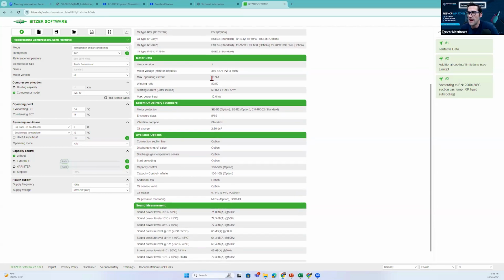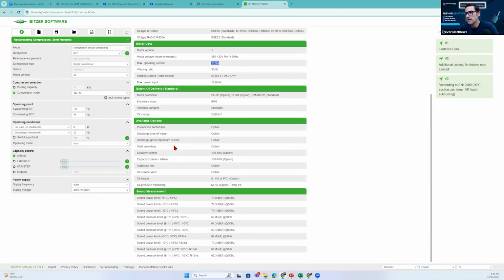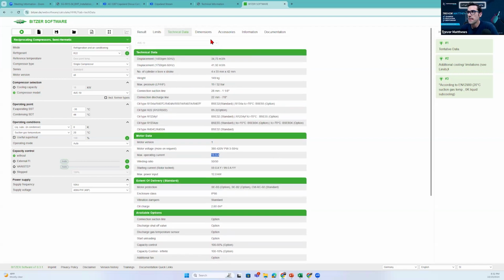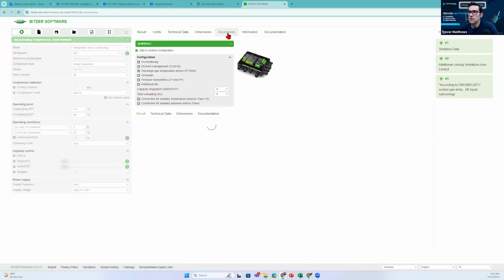And what does that mean? Maximum operation current. Well, that's the max that compressor will run before the internal overload will trip. So if this compressor is, say, running at 22 amps, it's going to trip off on its internal overloads. And then it'll talk about the different options down here. So I don't see, it just says additional fan. So if we go to accessories, this is where it's going to come in.